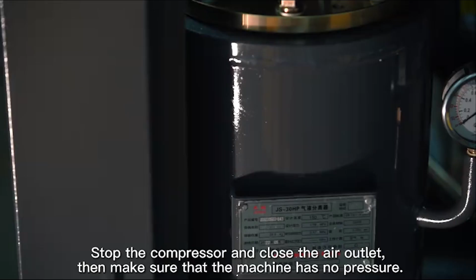When the LCD screen shows the separator is blocked, the oil gas separator filter must be replaced. It should be replaced every 2000 hours. If the operating environment is poor, its life will be shortened. The replacement steps of the separator filter are as follows.